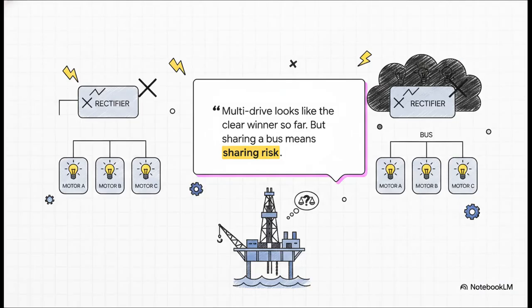If you're an engineer watching this, you're probably sitting there wondering, okay, why would anyone ever spec a single drive system if multi-drive is this good? Well, there is a massive operational catch. Multi-drive looks like the clear winner so far, but sharing a bus means sharing risk. If that one shared rectifier trips, every single motor downstream goes dark simultaneously. In a single drive setup, losing one unit only ever takes out one motor.